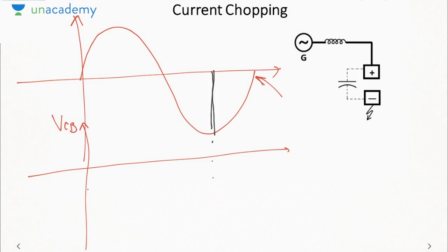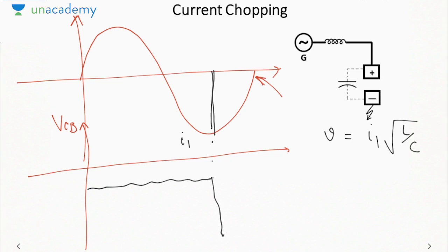So up to this point the circuit breaker voltage will be less. As soon as we interrupt the arc at a current I, let us say I1, the circuit breaker voltage will be V equal to I1 under root L by C, which was the prospective voltage. Suddenly a high voltage occurs, and the current will become 0. So up to here the graph will be like this. Then current suddenly becomes 0. But due to this high voltage, what will happen? The arc will restrike and current again begins to flow. So current again becomes non-zero, voltage becomes low.